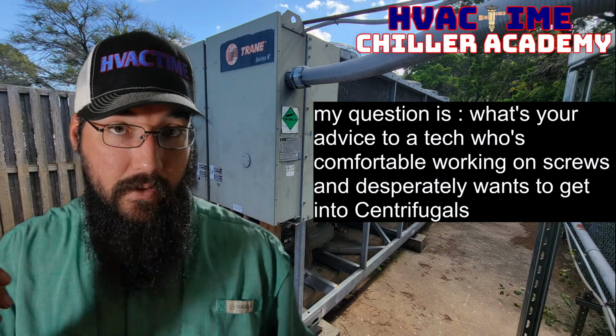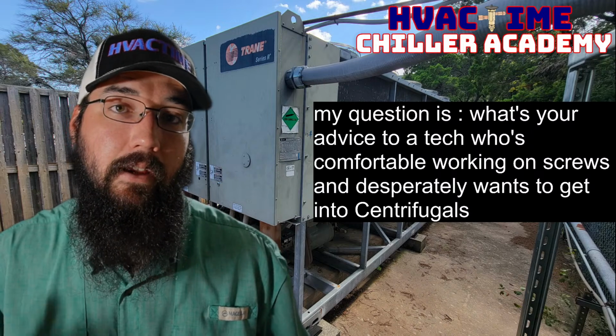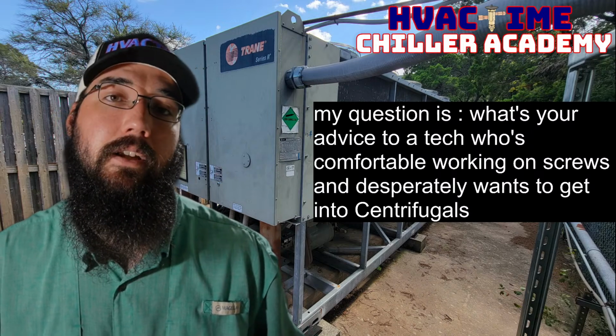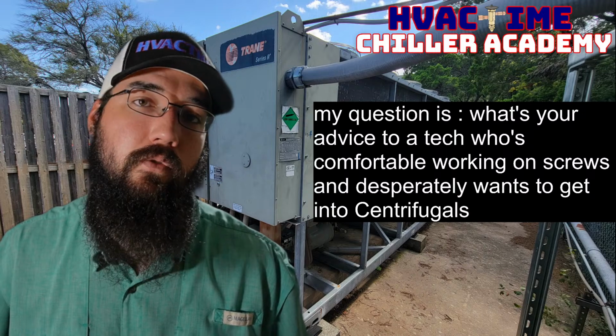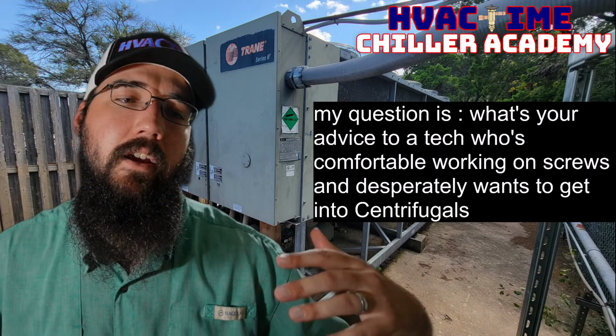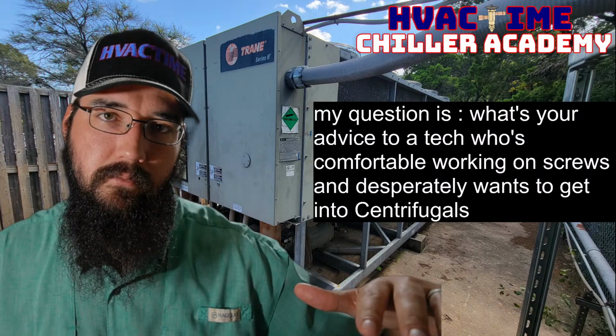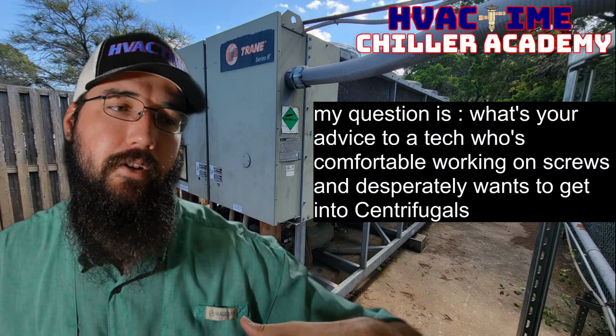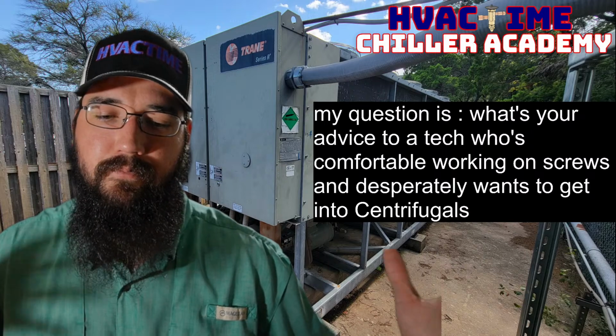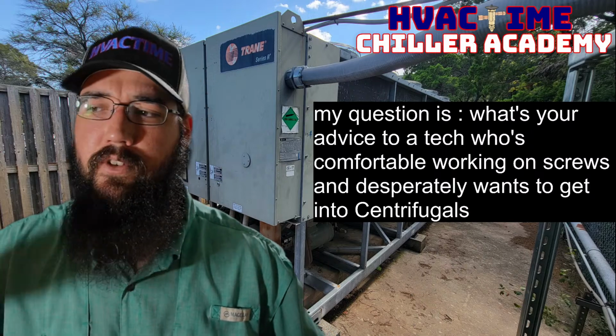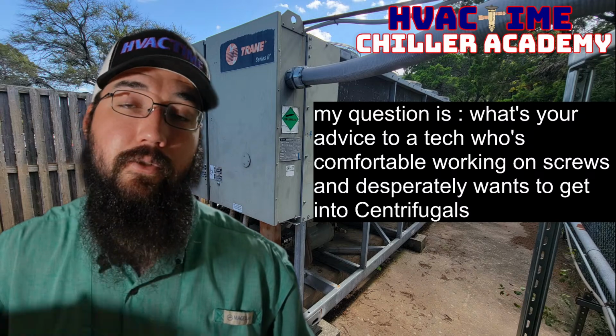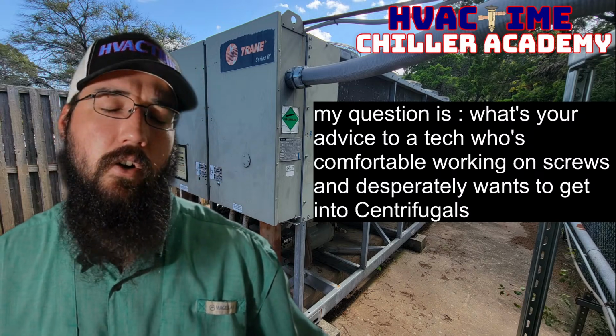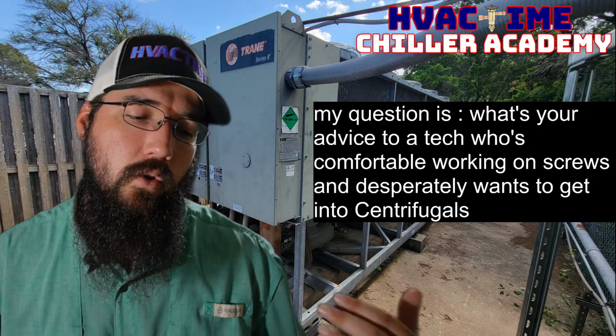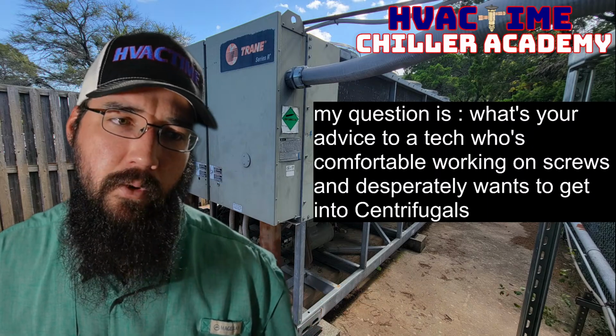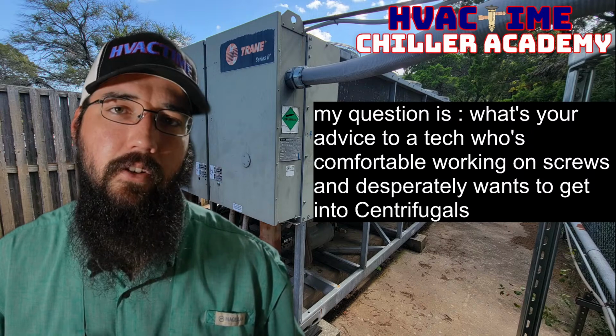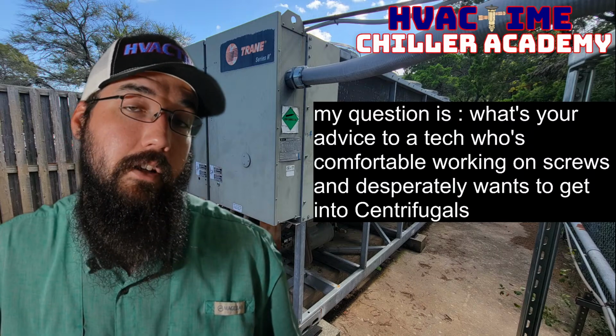So, for example, leaving a valve closed on the eductor assembly and allowing the evaporator to start stacking on the oil migration or the oil level stacking in the evaporator, that causing low heat exchange issues, which eventually could lead to liquid refrigerant droplets getting pulled into the evap or into the compressor, which will shred it, or you change a set point incorrectly. I mean, I could go down a list here, right? There's lots of things you could do wrong because you just genuinely didn't know any better.